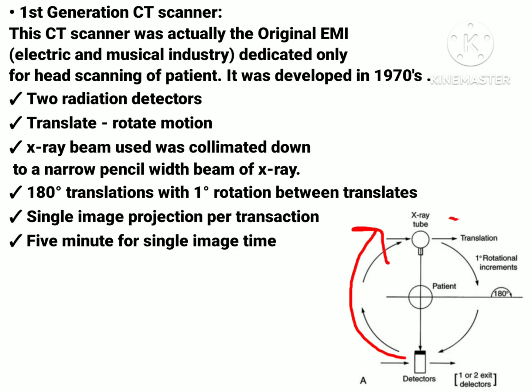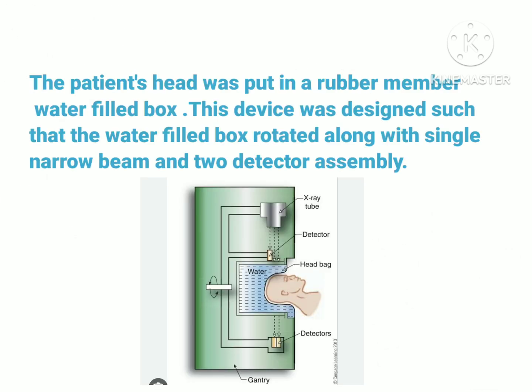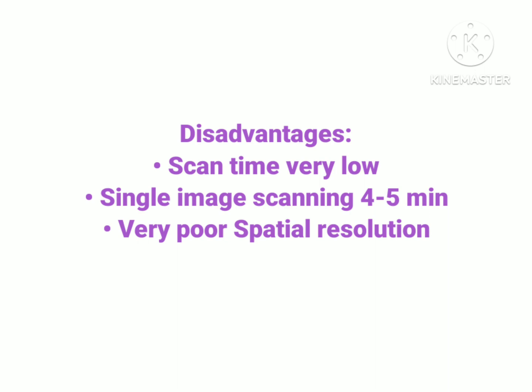In one translation, one single image is being projected. In this EMI CT scanner — the first generation CT scanner — the patient's head is put into a rubber membrane inside a water-filled box. You can see how the patient's head is placed into the water-filled box. This device was designed such that the water-filled box rotates along with the single narrow beam and two-detector assembly.